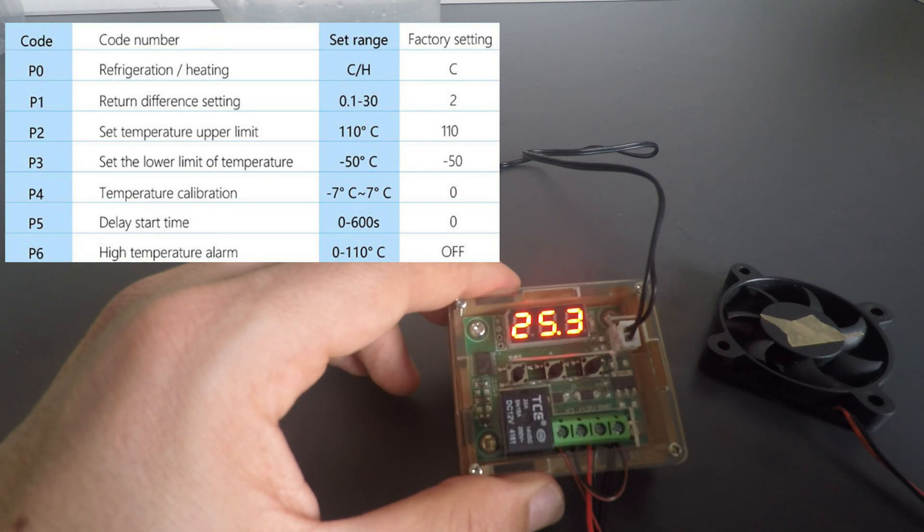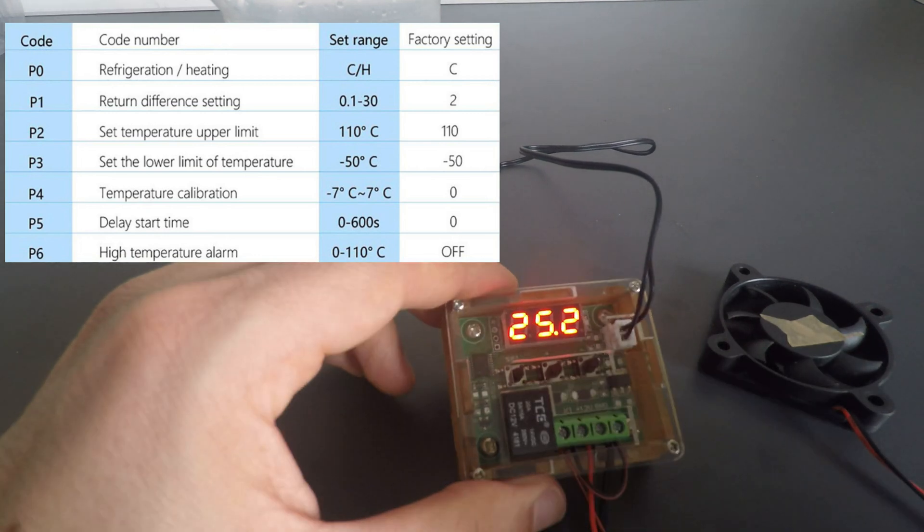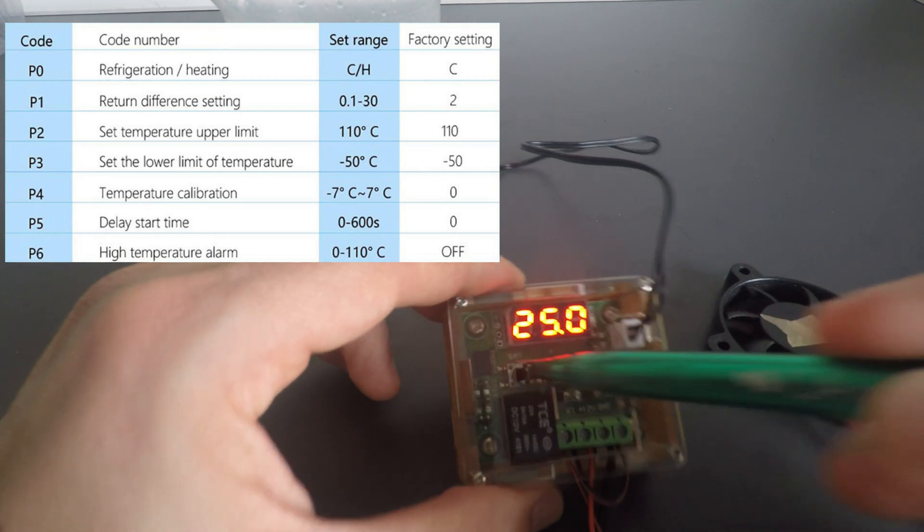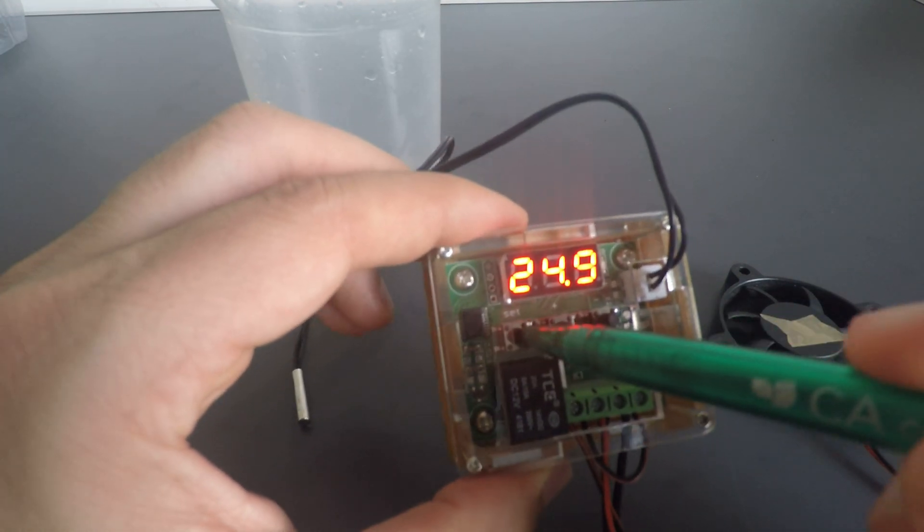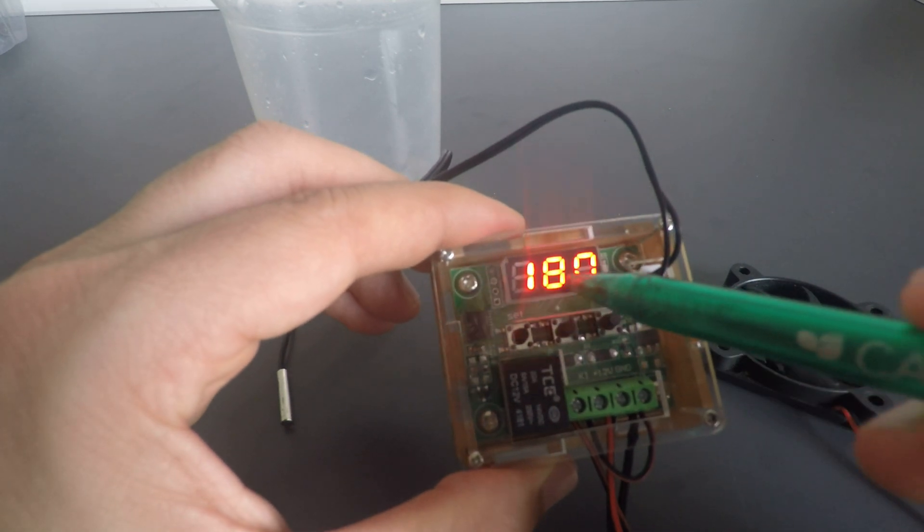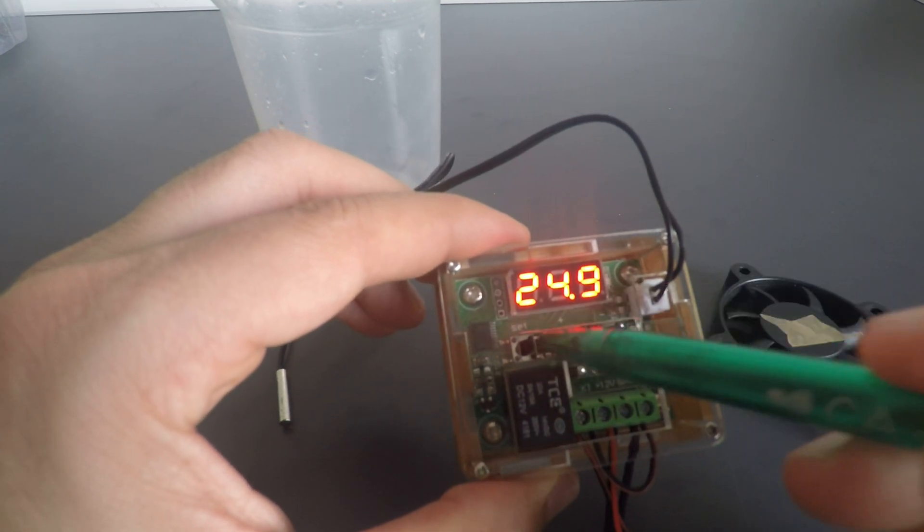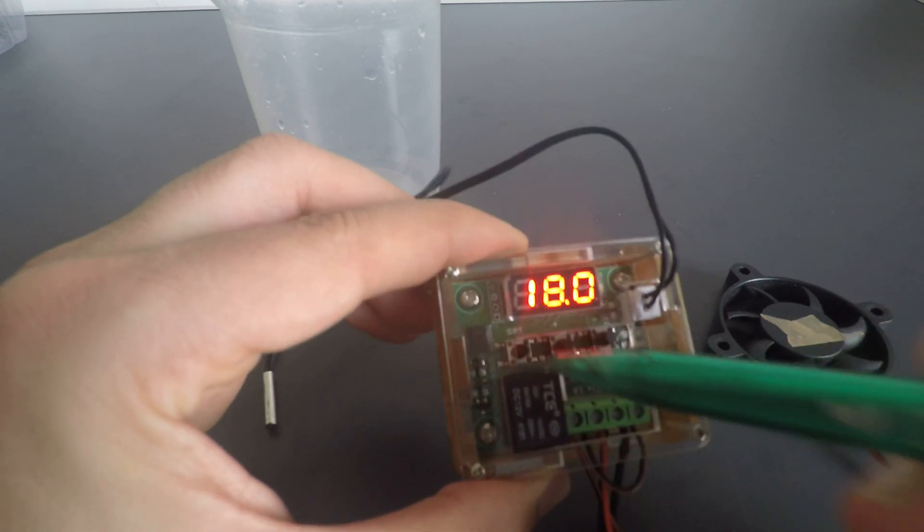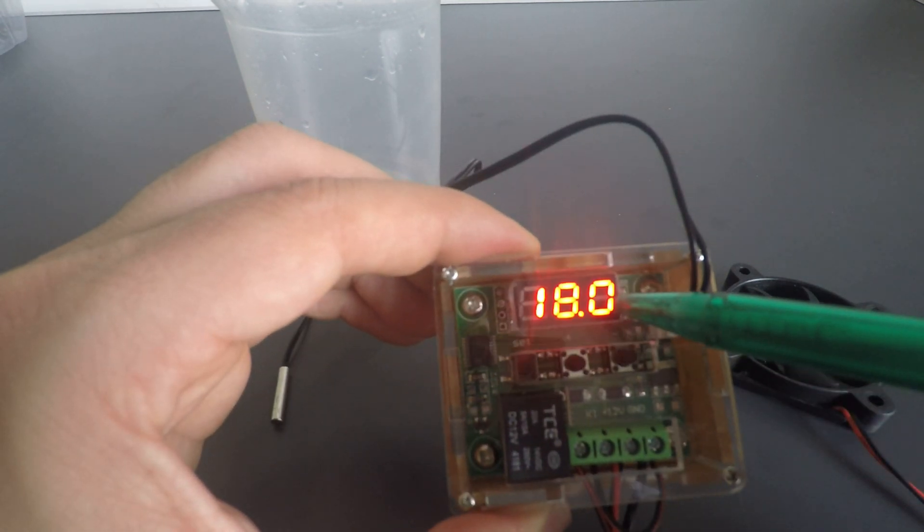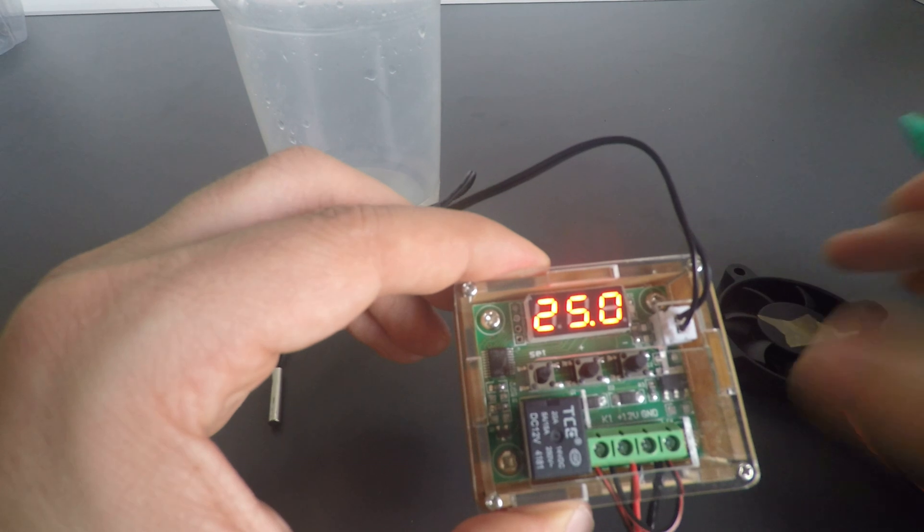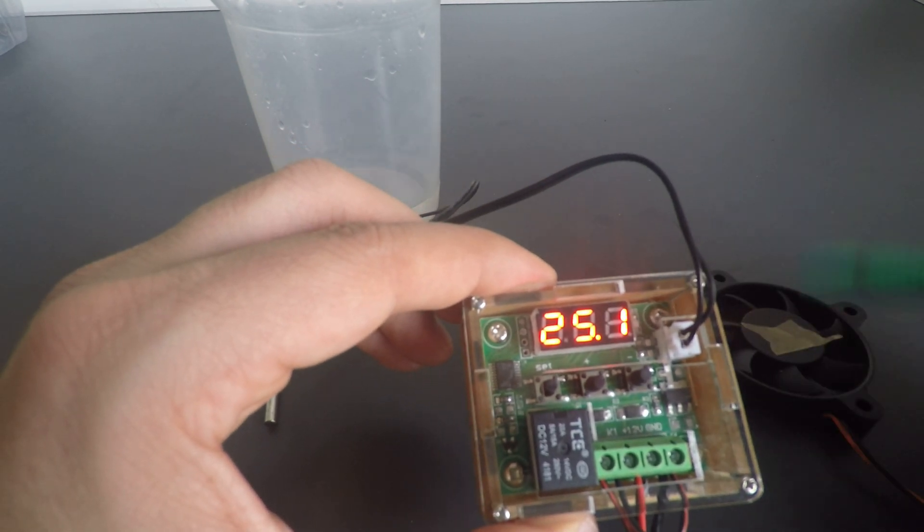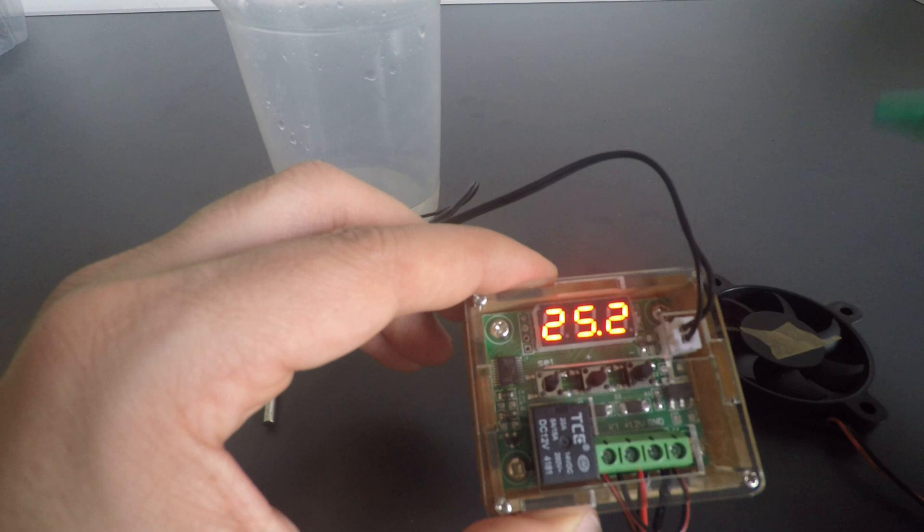And I was struggling with that, and what I found out is if you press this button which is set, only once it's gonna flash. This is 18 degrees, this is actually the trigger. I'm gonna press once more so you can see this is actually the trigger for which the temperature will start the fan.